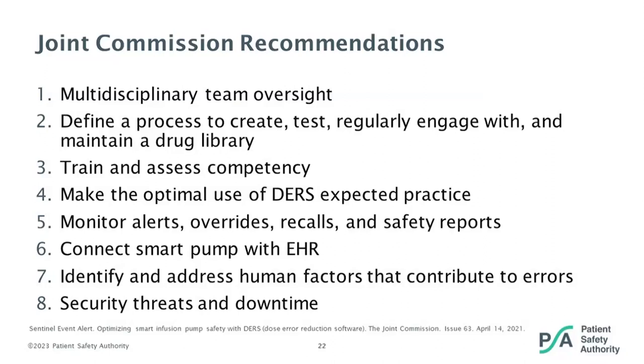It should be obvious if an infusion is running outside of the guardrail's profile. Next, monitor for smart pump overrides, adverse events, and near misses — this information should be used to evaluate drug library settings and pump program processes. If possible, interconnect the smart pumps with the electronic health record. The seventh recommendation is evaluating for human or environmental factors that contribute to pump programming errors. The last suggestion is to protect the pumps from cybersecurity threats and develop downtime procedures when interoperability or wireless programming is unavailable.